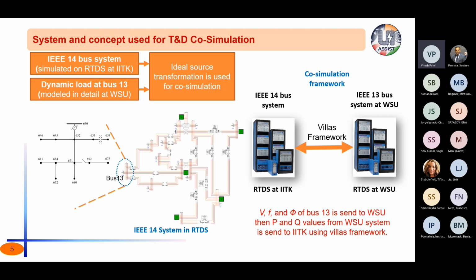The concept and the system used for the T&D co-simulation was that we simulated two systems. One was the IEEE 14 bus system, which was simulated at IITK in the RTDS system, and one was the IEEE 13 bus system, which was simulated at the WSU campus. In the IEEE 14 bus system, bus 13 is modeled as a dynamic load, which will get the real and reactive power from the model of the IEEE 13 bus, which was simulated at WSU. And the main idea is ideal source transformation used for the co-simulation.